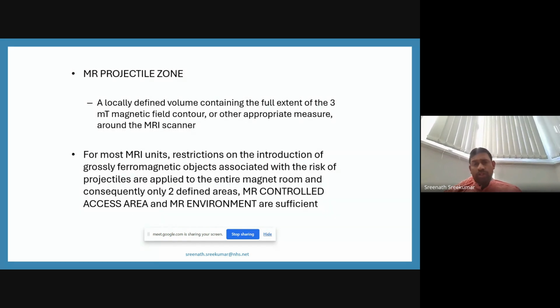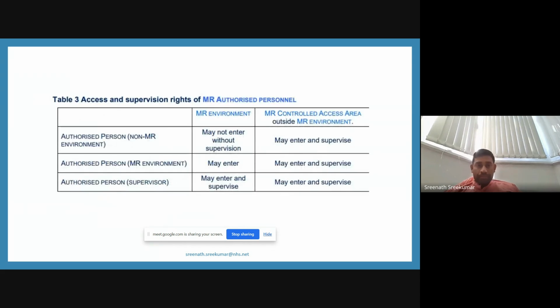Going to the projectile zone, the risk is that there is a projectile risk from the equipment or the implant. Anything ferromagnetic will have attractive forces toward the scan room. Consequently, the MR controlled access area does not involve that much risk, but the MR environment is the area with the most risk involved.